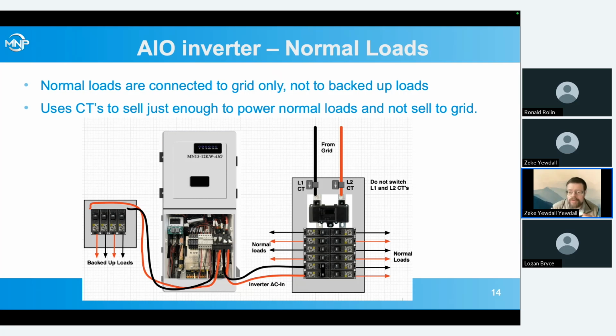What it'll do is it'll see a spike going back to the utility through those CTs and say, oh, I got to reduce that power level. It does that pretty quick, but not fast enough for some of the new smart meters. And the utility will say, you were selling power, you weren't supposed to. So to avoid that, we can set it between 30 watts and 300 watts. In a typical house, I find that usually 100 to 150 watts is enough to prevent sellback, but it really depends on what loads you have and how fast they tend to change and what kind of loads they are.